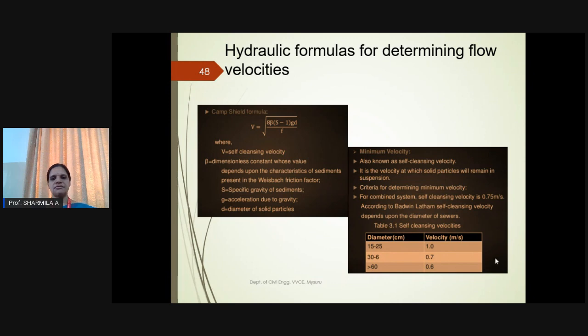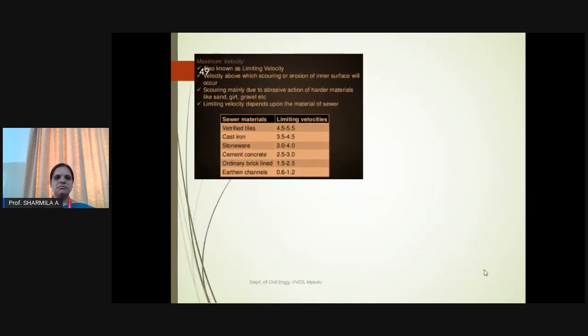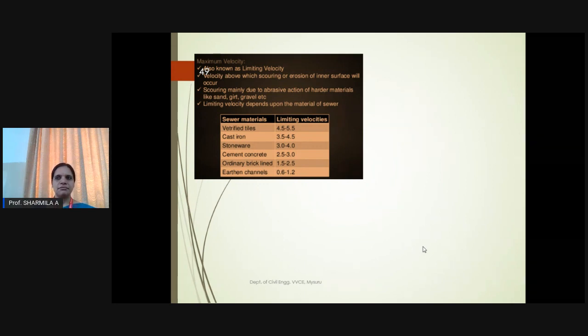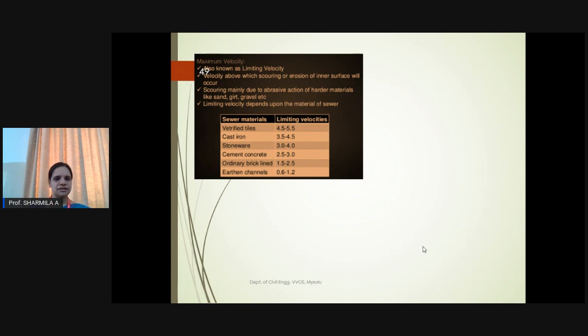The minimum velocity to be maintained is that at which solid particles remain in suspension. For combined sewers, the minimum velocity is 0.75 m/s. From the table: for a sewer diameter of 15–25 cm, the minimum velocity is 1 m/s. Maximum velocity is also known as limiting velocity; if velocity increases, abrasion of materials takes place due to soil, sand, grit, and gravel. For vitrified sewer material, limiting velocity is 4.5–5.5 m/s; cement concrete 2.5–3 m/s; ordinary brick-lined 1.5–2.5 m/s; earthen channels 0.6–1.2 m/s.